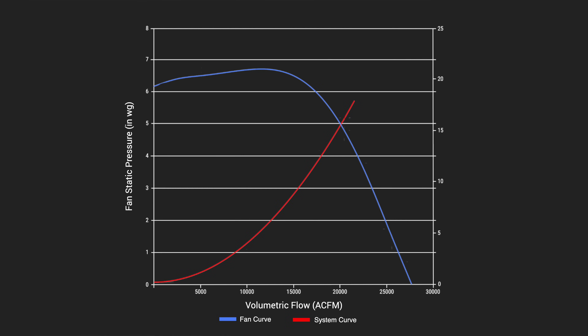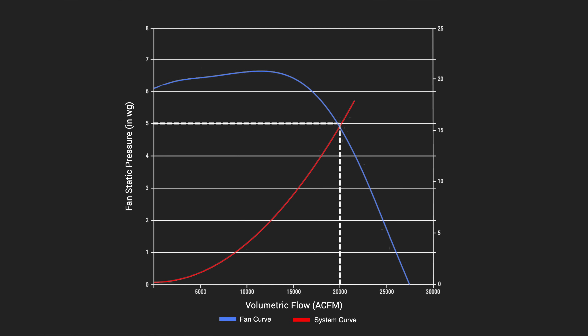This means that to deliver 20,000 CFM in that system, the fan has to generate 5 inches of static pressure to overcome the system's resistance to its airflow. By knowing the amount of system resistance at a particular amount of airflow, the system's resistance to other quantities of airflow can also be determined using the fan laws, provided no other variables change in the system, such as closing a damper.